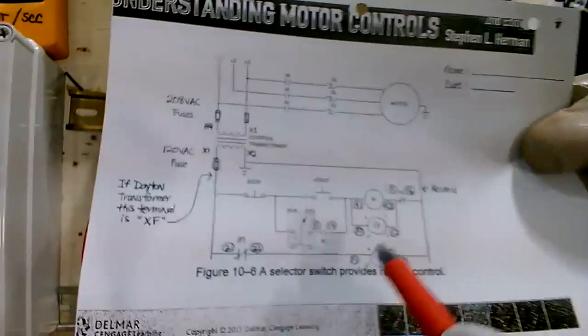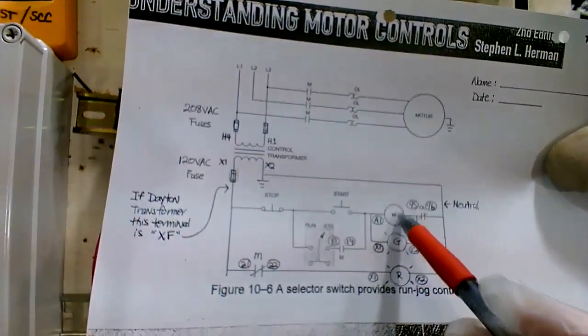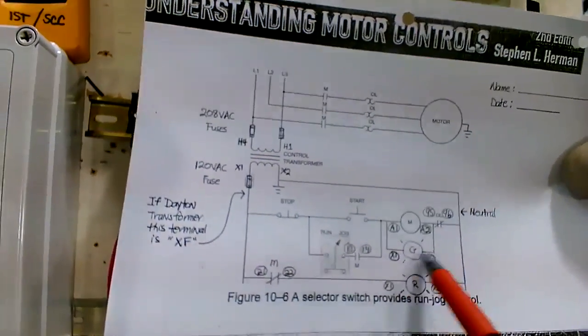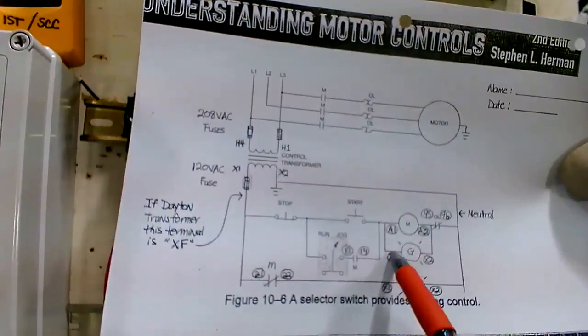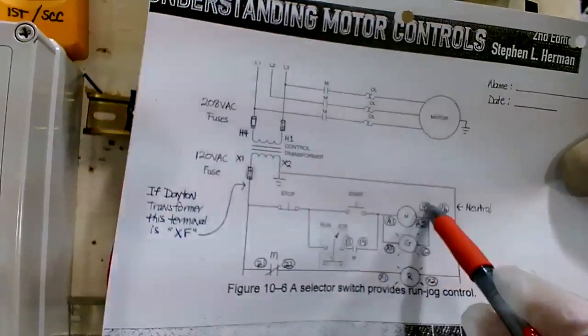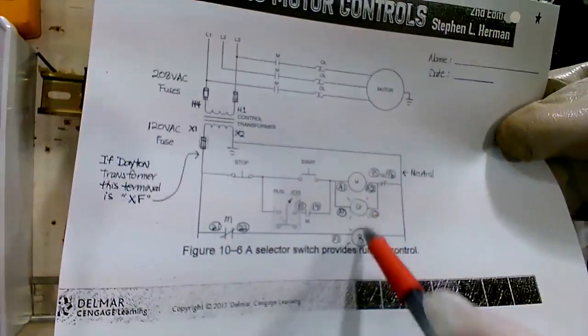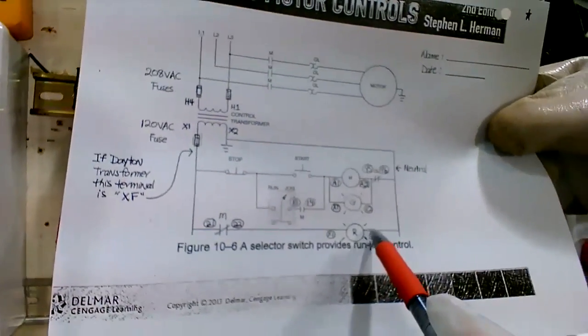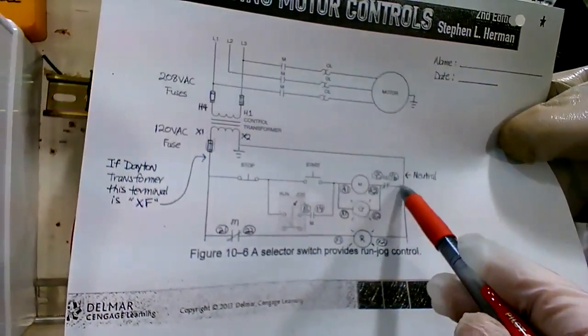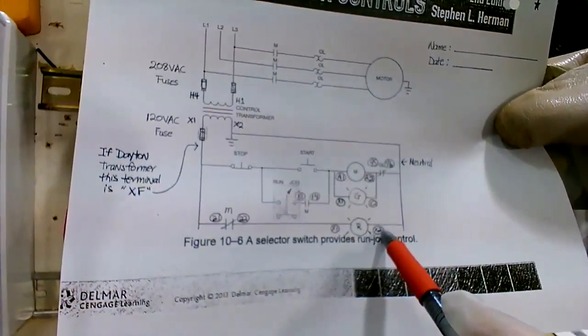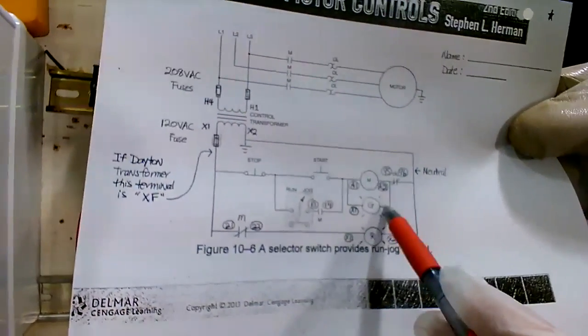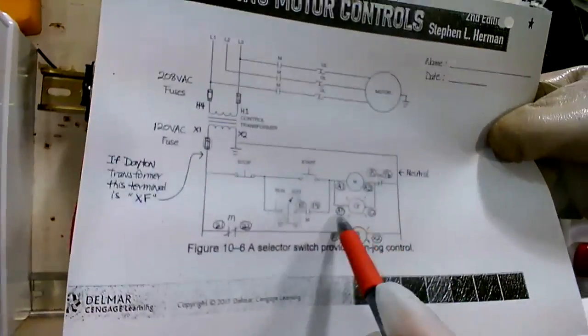So what he's adding now is a green light in parallel with the coil. The green light has those two terminal markings on it, and you're going to wire it to the A1 and to the A2 or to the 95. The red light is the X2 on it, the neutral. It's going to hook with the 96. On the neutrals for the lights, they're going to be white wires, and on these, they can be black or red on the tops of the wires.